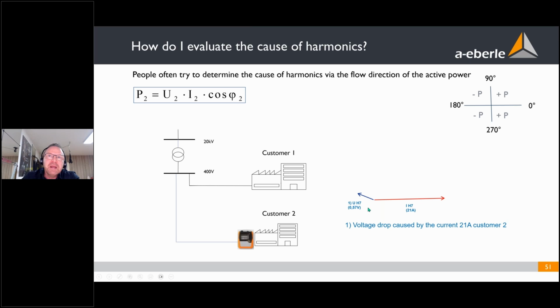And now normally we expect to get the angle between the voltage drop and the current. So if this angle is bigger than 90 degrees, this means this customer is responsible, he is producing the 7th harmonic. But the analyzer is connected here. We only see what is the result of the 7th harmonic here of all producers of the 7th harmonic in this grid. Out of the medium voltage network, we always get the 7th harmonic. The transformer transfers the 7th harmonic one by one.